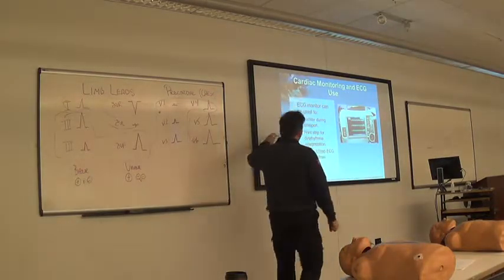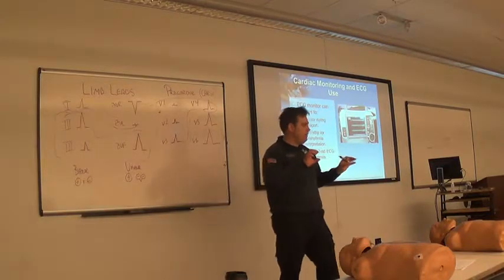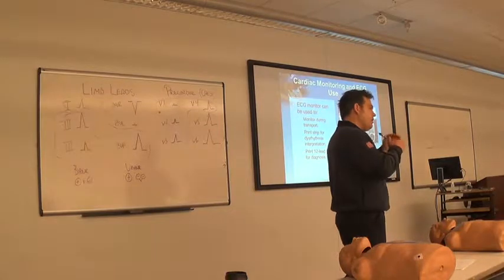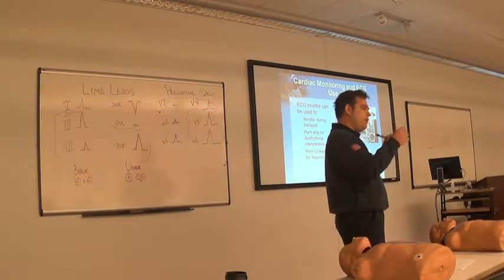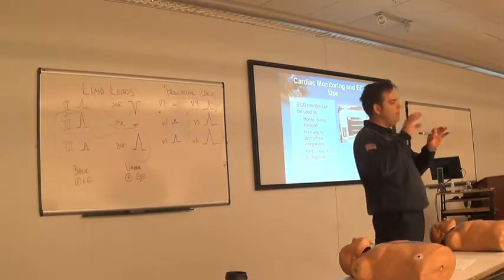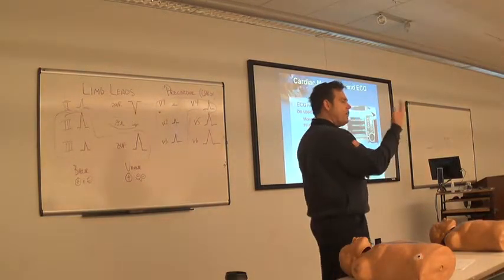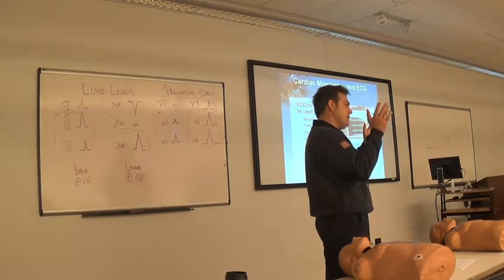When we monitor, we utilize a completely different frequency. All right? And so when we monitor, we have less artifact, but we don't have as clear of a picture as we would if we were moving to 12 lead mode. Okay? So it's just like I'm reading. I can say, yeah, I can read this thing. It's not crystal clear, but I can see it.